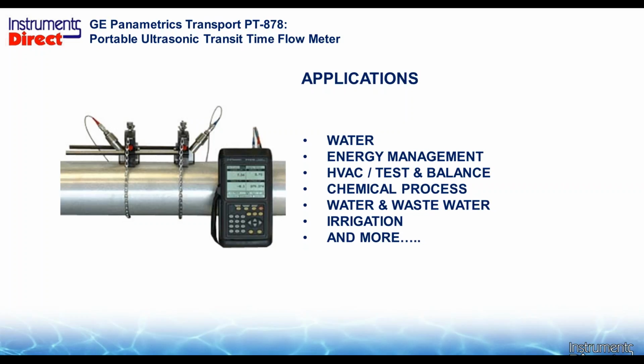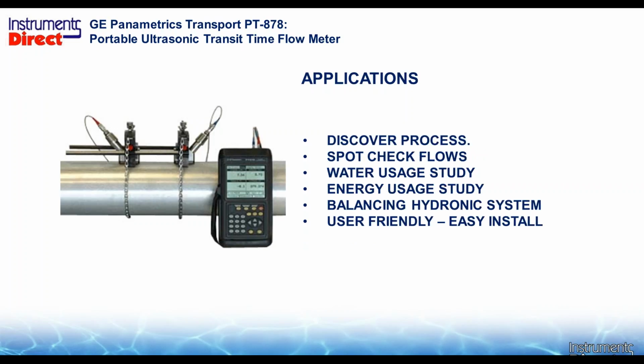So for any aqueous application, a clamp-on transit time flow meter is your guy. You can use it for water management, energy management, HVAC test and balance, chemical process, water and wastewater, irrigation, and the list goes on and on. There are some advertised clamp-on airflow meters, but they're pretty much not for the world that you and I are in. They're for exotic high-pressure metal applications. So if you have a compressed air application, this is not the technology for you at this point in time. Wish it was. It's not quite there. So stick with your liquid application, especially with the PT878 and other variations of it.